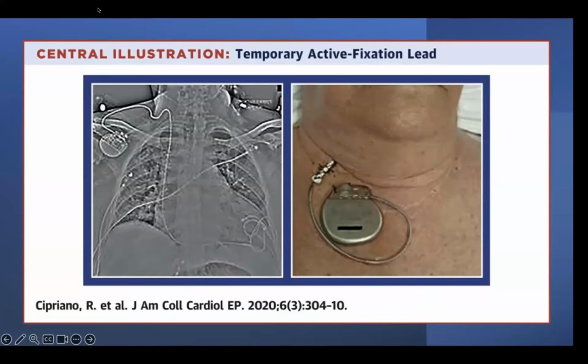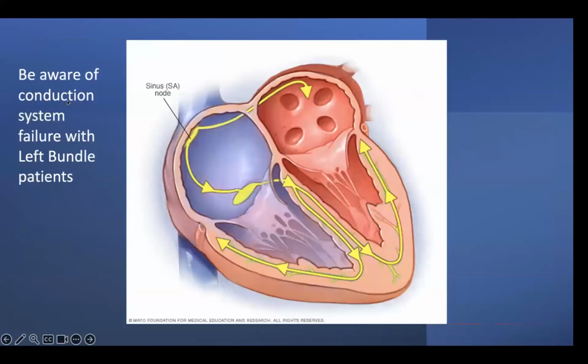Perfect. So one of the things you mentioned, that was a really good example of how you kept the device pacing by using the 2 leads strategy, right? You use the lead you'd use for the right atrium as a temporary pacing wire. That's correct. Brilliant. And I'd always recommend having some way to keep the pacing going. Things to keep in mind when you are using 2 different pacemakers, like an external pacemaker or the old device and the new device: if they're not set asynchronous, then they could be over-sensing, or they could sense a pacing spike that's not capturing and cause inhibition on the other device.